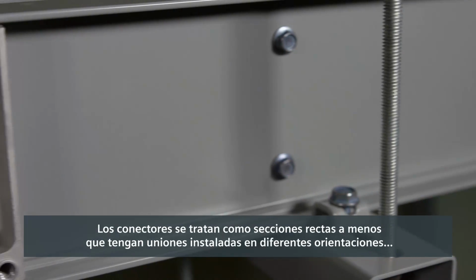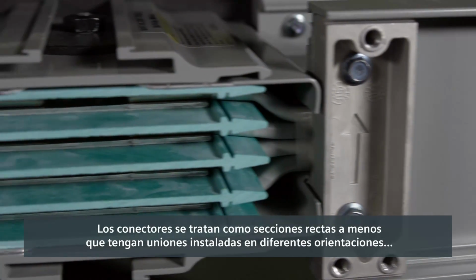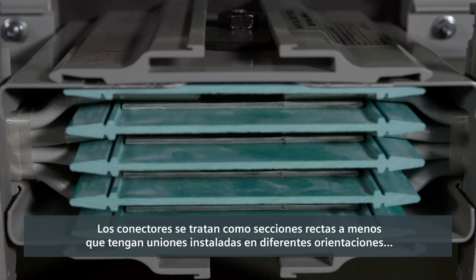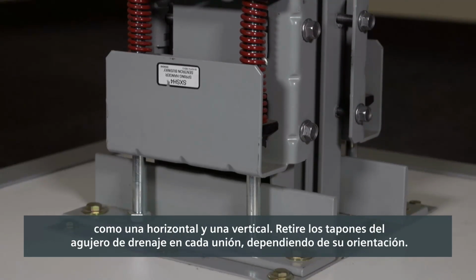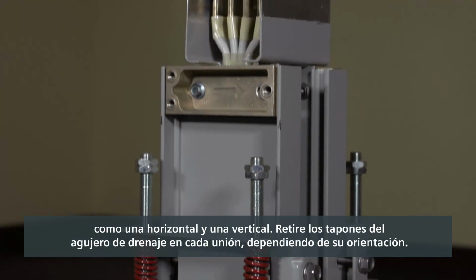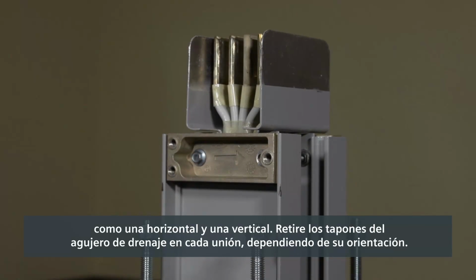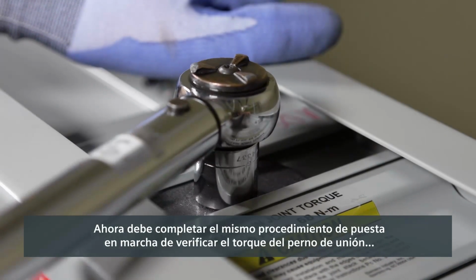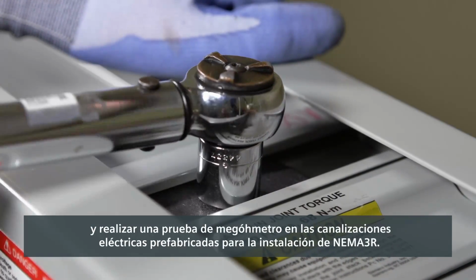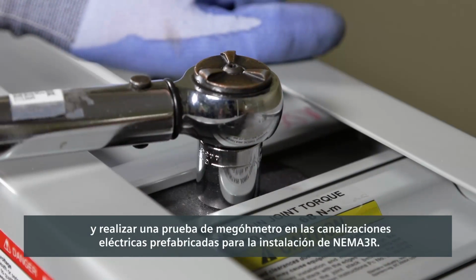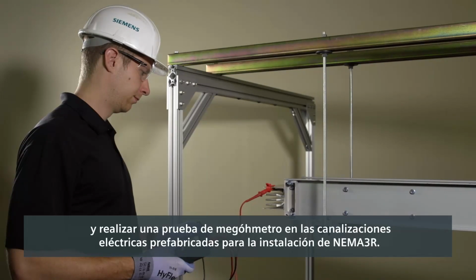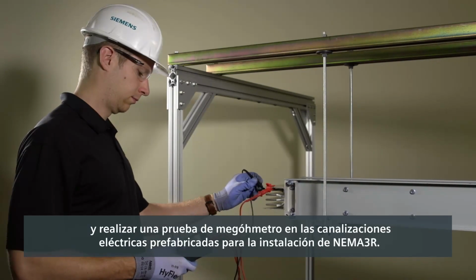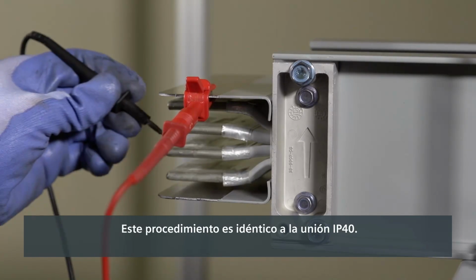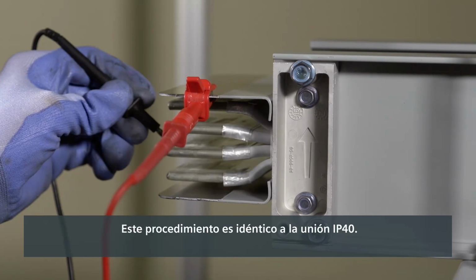Fittings are treated like straight sections unless a fitting has joints installed in different orientations, such as one horizontal and one vertical. Remove the drain hole plugs at each joint depending on its orientation. The same commissioning procedure of checking joint bolt torque and performing a Megger test on the isolated busway run must now be completed for the NEMA 3R installation. This procedure is identical to the IP40 joint.